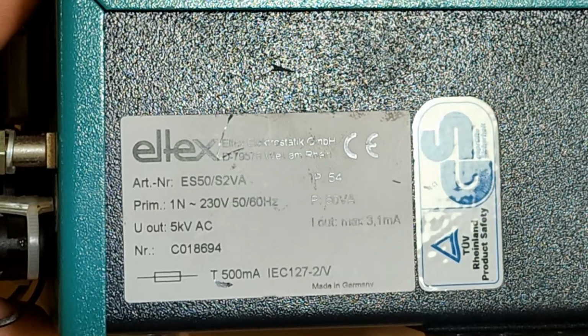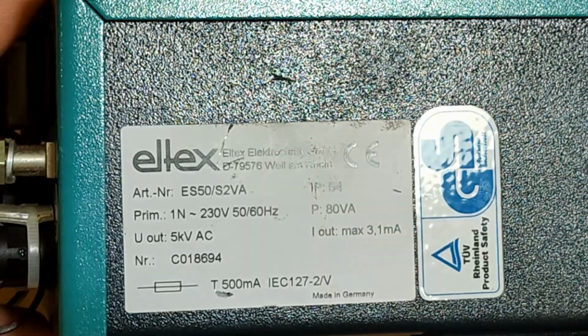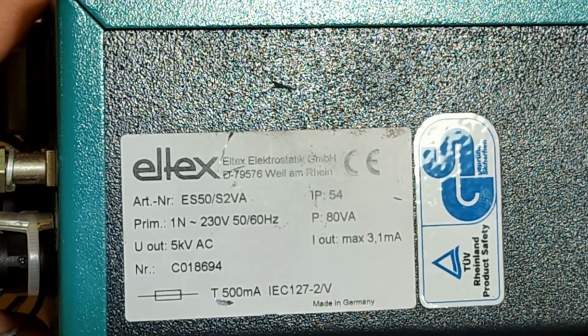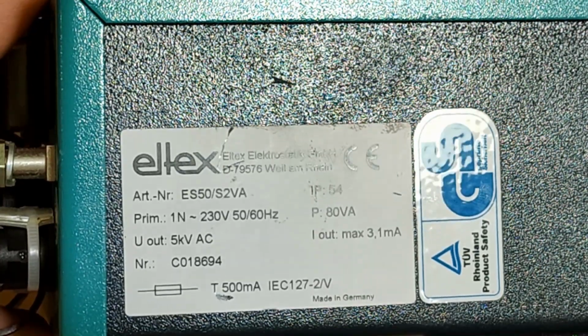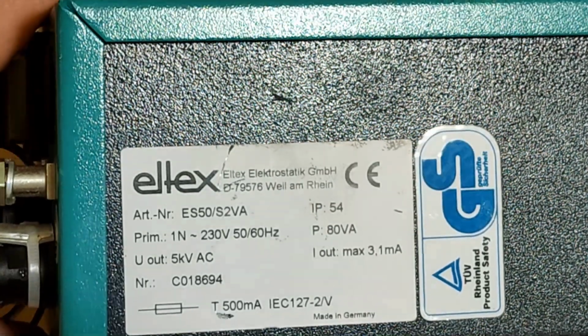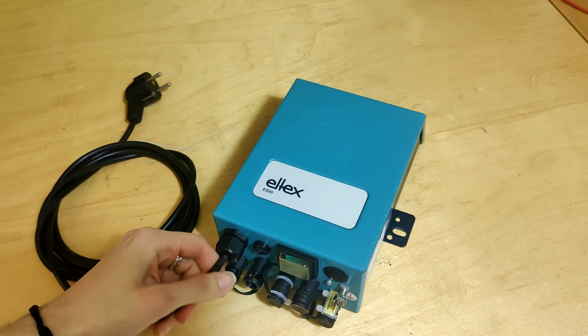Here I've got some information about this unit: 5 kilovolt AC output, 230 volts primary, output maximum current is 3.1 milliamps, and total power of 80 volt amps. So let's turn it on first and see what it does.